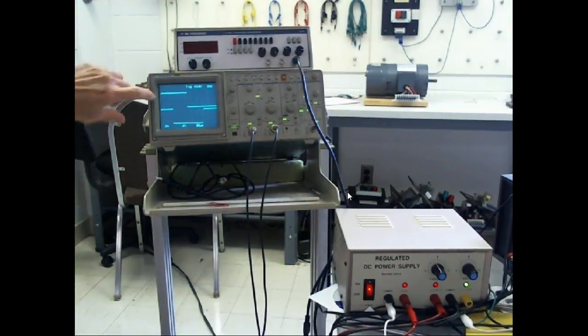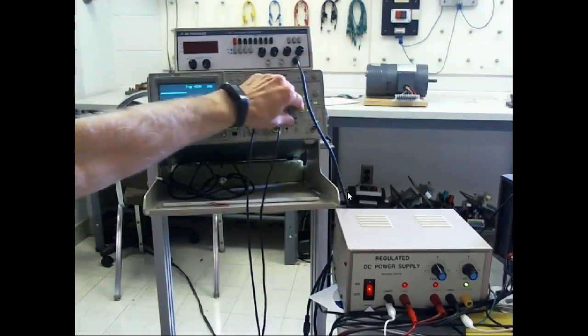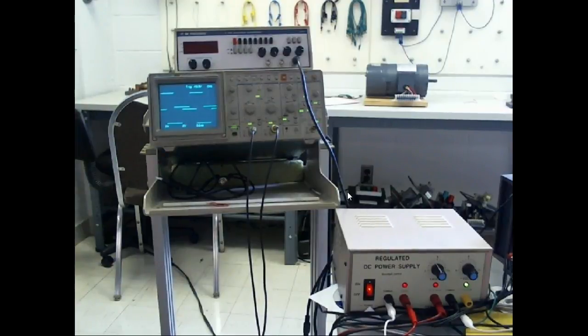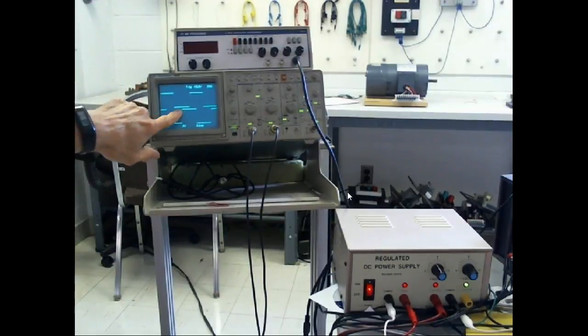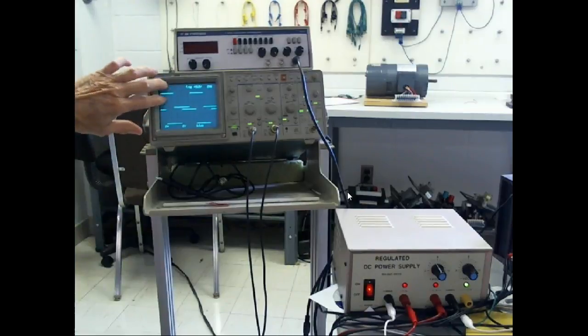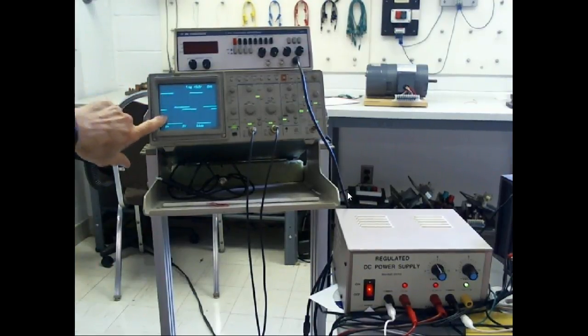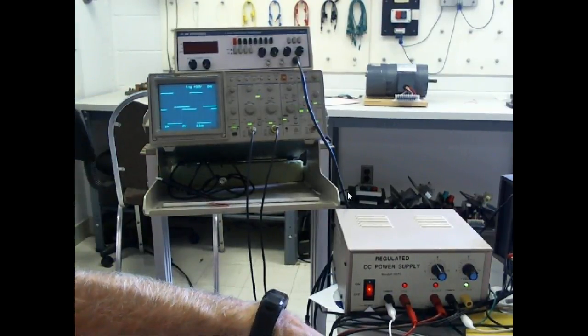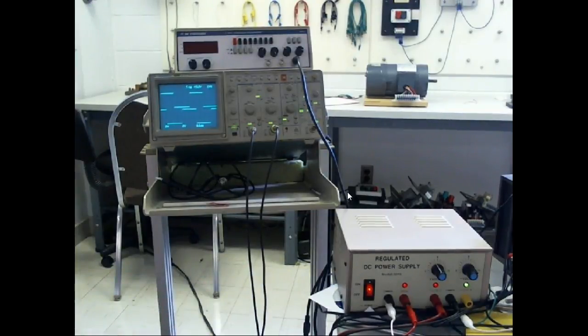So the leading edge, or the rising edge, is right here. I'm going to have to turn my scope down one notch so we can see one revolution. And hopefully you can see, this is channel one, sometimes called the A channel. This is channel two, coming off our quadrature encoder. What we can see right off the bat is they're 90 degrees apart, so this indicates what direction we're going. If channel A leads channel B, then that means we're rotating in the clockwise direction, and that's something we would have to figure out.